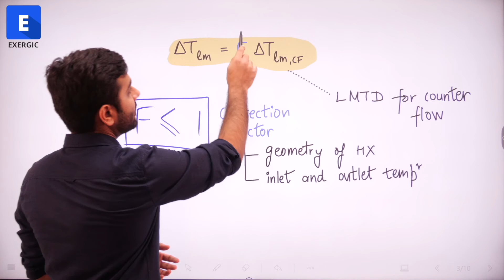When it is counter flow, this is how we write it. And when it is cross flow, just multiply that with F, because delta T for cross flow equals F multiplied by delta T of counter flow. So delta T is defined exactly the same as for counter flow: in the same configuration, this difference gives delta T1 and this difference gives delta T2.